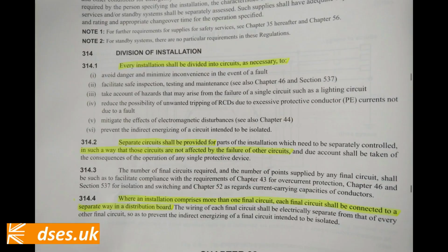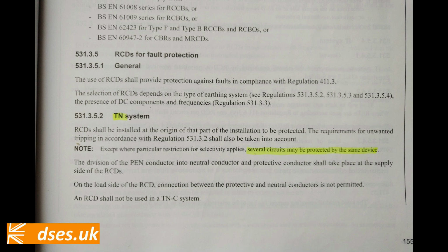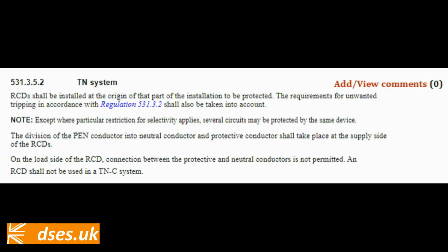That said, the whole RCD protecting multiple circuits thing never did sit well with sticklers for Regulation 314, which requires circuits to be segregated so that if one has a fault, it doesn't pull down anything else. An RCD protecting a group of circuits represents a single point of failure for that group. And although 18th edition laid that argument to rest in 2018 by introducing new regulation 531.3.5.2, specifically permitting a single RCD to protect multiple circuits in a TN system, it's telling that in the amendment to DPC, this has been dropped, with the wording changed to say RCDs shall be installed at the origin of the installation, and no mention of them serving multiple circuits anymore.